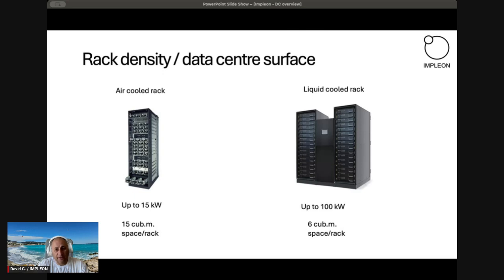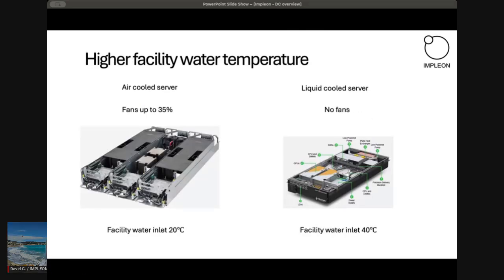However, there is another important thing, the facility water temperature. With the air-cooled approach, we need 20 degrees facility water to have 25 degrees in the cold aisle. With liquid heat transfer, we can have 40 degrees, and it will be enough to cool each component of the server. Another important thing is that in this case we take away the fans and their energy consumption. In the new generation of servers, it can be up to 35%. So 35% of the rack power goes just to supply fan energy.